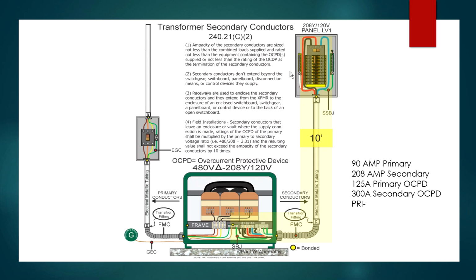Well, this is what it supplies, and it terminates right here. They don't go anywhere else. So this rule is met. Okay. If this had just been an enclosure with a disconnect in it, and just one disconnection means, again, as long as it doesn't leave this enclosure, this panel board, or whatever this disconnection means, then it's okay. It stops right there. Next, 3.